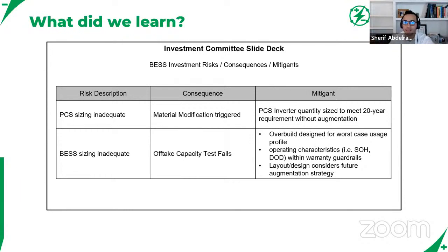So I think that's mainly because most of the time there's not really a technical dive into how you're going to do things. It's just more of a business review. But on our side at Duke Energy, recognizing the potential risks with the current DC augmentation strategies, we made a decision for now to stick with AC augmentation until we get more comfortable with DC augmentation, if the risks go down.